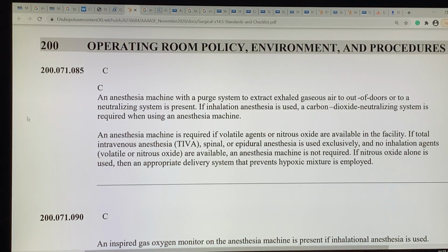Anesthesia machines kind of come one size fits all, but it depends—there are standards. Almost all of them that haven't been taken apart would carry these requirements: 0.85, an anesthesia machine with a purge system to extract exhaled gaseous air outdoors or to a neutralizing system is present. If inhalation anesthesia is used, a carbon dioxide neutralizing system is required. An anesthesia machine is required if volatile agents or nitrous oxide are available in the facility. If total intravenous anesthesia, spinal, or epidural anesthesia is used exclusively and no inhalation agents are available, an anesthesia machine is not required. If nitrous oxide alone is used, a proper delivery system that prevents hypoxic mixture is employed.